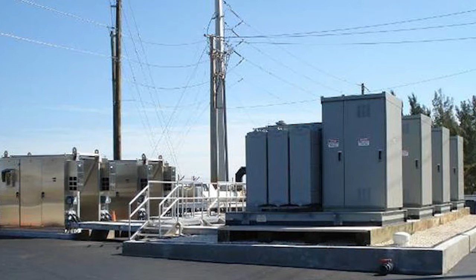I like this picture because it graphically shows what I'm talking about. On the left is a 10 megawatt installed system with process heaters, control panels, and SCR control panels—a lot of equipment, a lot of time. To the right is just the transformers needed to run that 10 megawatt system. They're bigger than the heater and panels, more expensive, and the time to wire up and install is tremendous. With this medium voltage technology, everything on the right goes away.